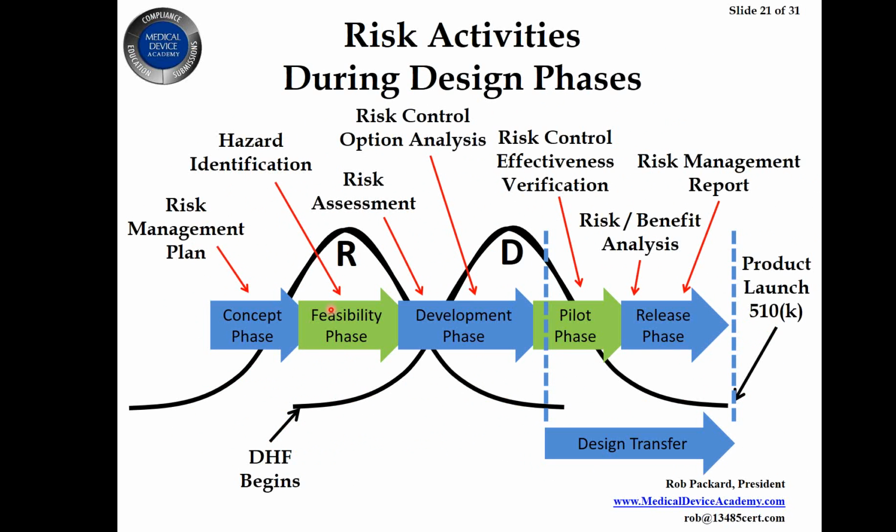I cover that in some of my risk management training, but things to look at are ISO 14971. Look at Annex C, has a bunch of questions. Annex E has a systematic way of identifying it. And then, of course, you can look at the MAUDE database for adverse events and identify Pareto analysis of failures of devices that are in a similar category.